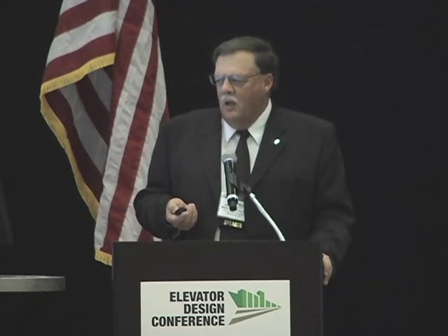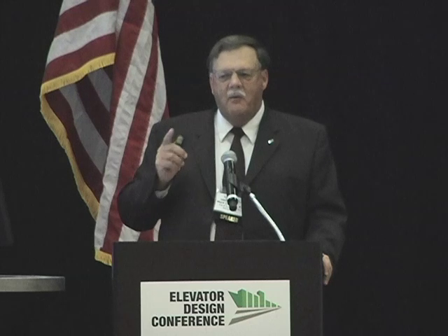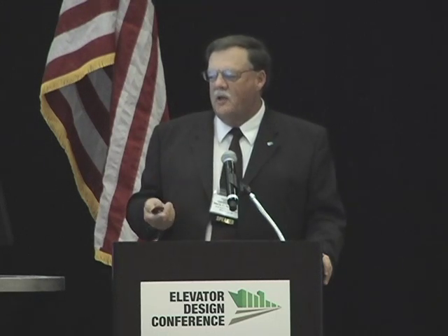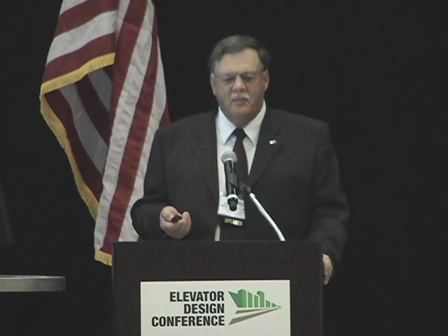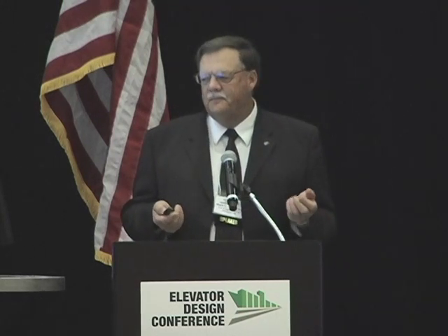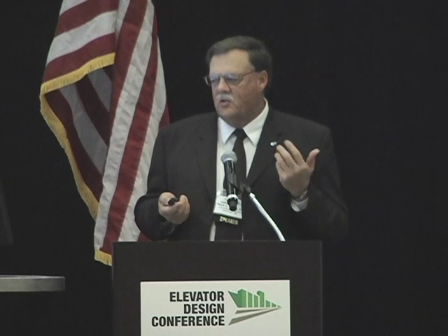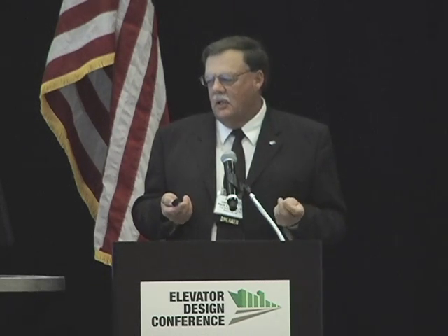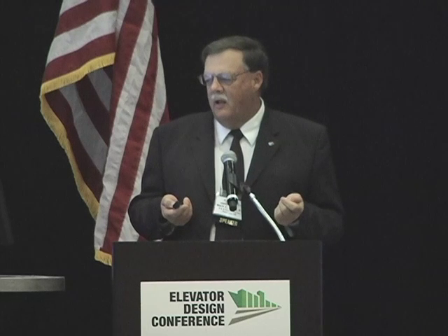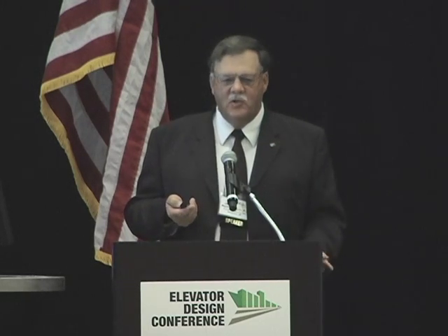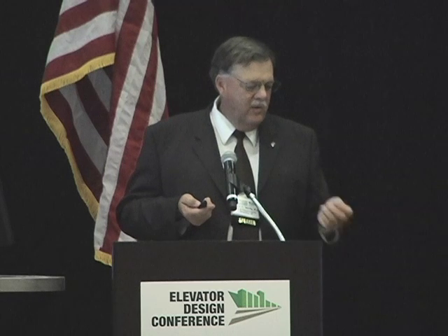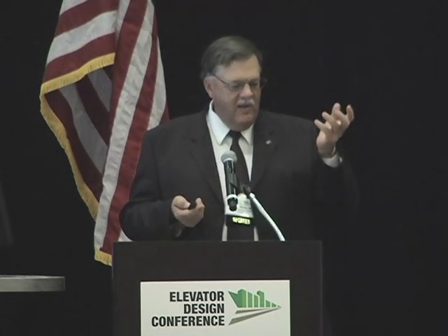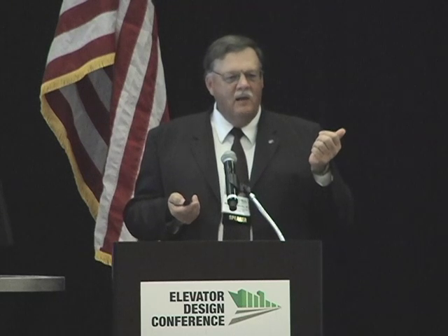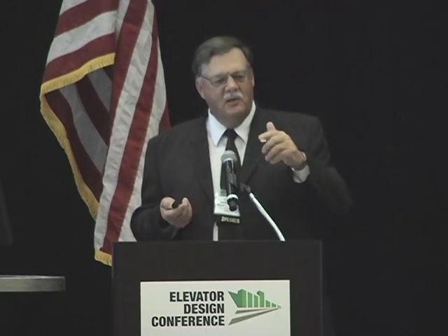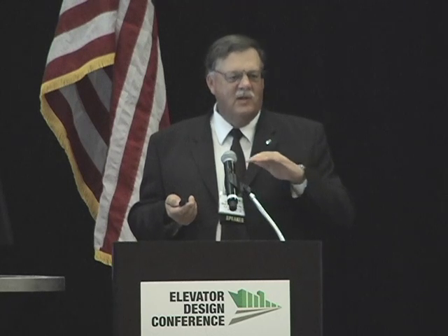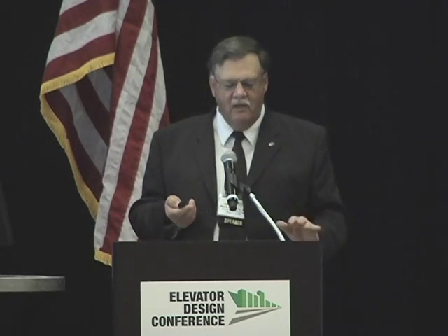So the other thing I like is what I call kind of a hybrid system, which is the high resistance or high Z grounded system. This kind of has the benefits of both systems. It's still grounded, but it gives you continuity of service because it's easy to alarm the system and helps control overvoltages. One of the problems with the delta systems is when you get a ground at one phase, the other two phases go up to 480 volts to ground, and you find another weak point in the system on insulation, and it punches through the insulation somewhere else, and you have that other ground, and things just go to hell in a handbasket.